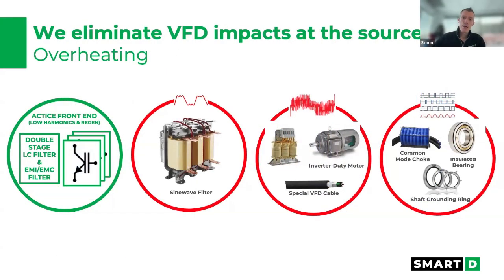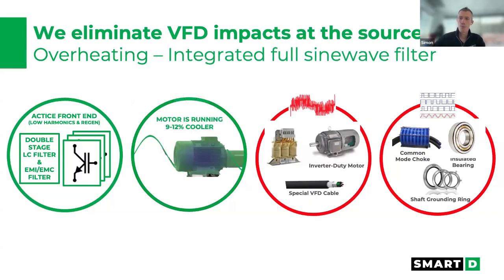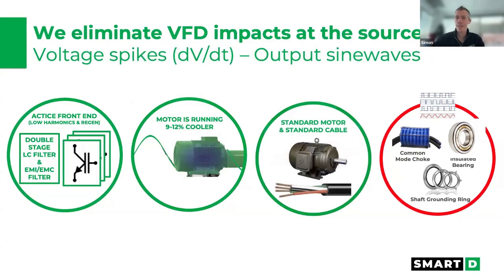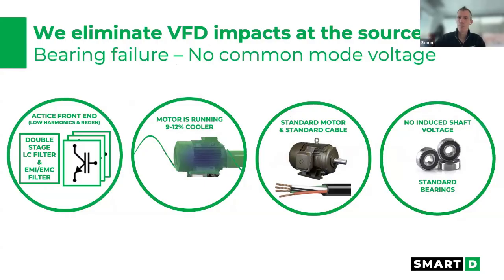So again, we take out the mitigation. So you don't need a sine wave filter. It's built in. Your motor runs cooler and quieter. You don't need to upgrade your motor for an inverter duty motor. You don't need to change your cable. You can use it as is. It will work. And you don't need to think about how to mitigate common mode that will kill my bearings over time. We're reducing 95% of common mode directly out of the gate.